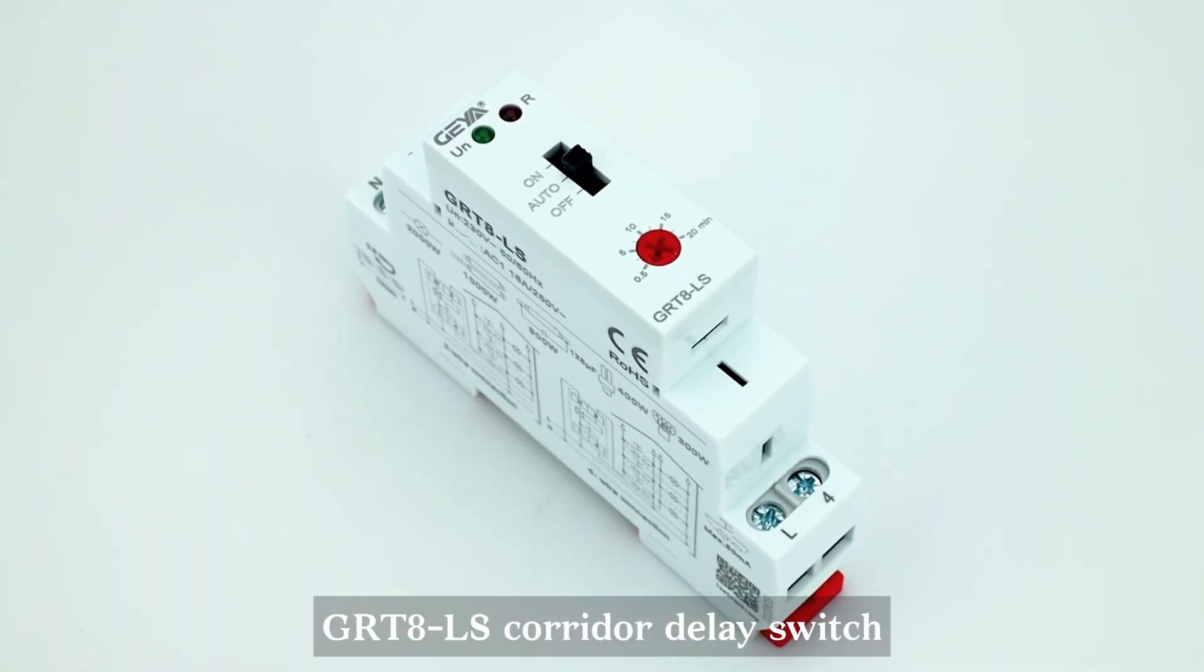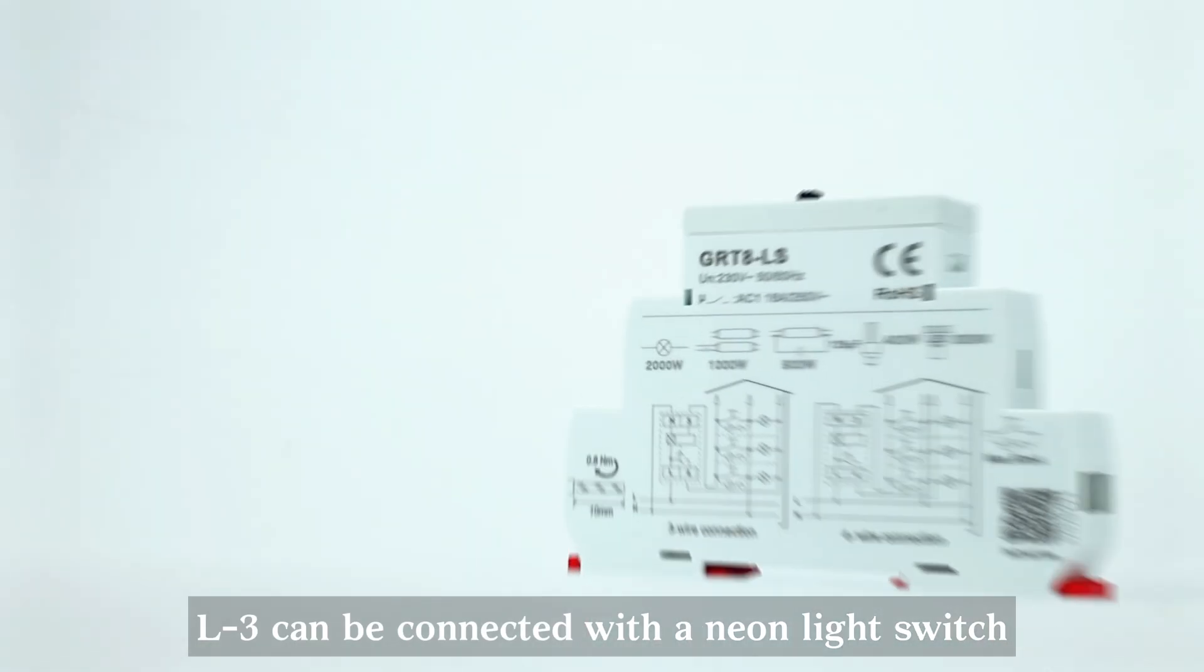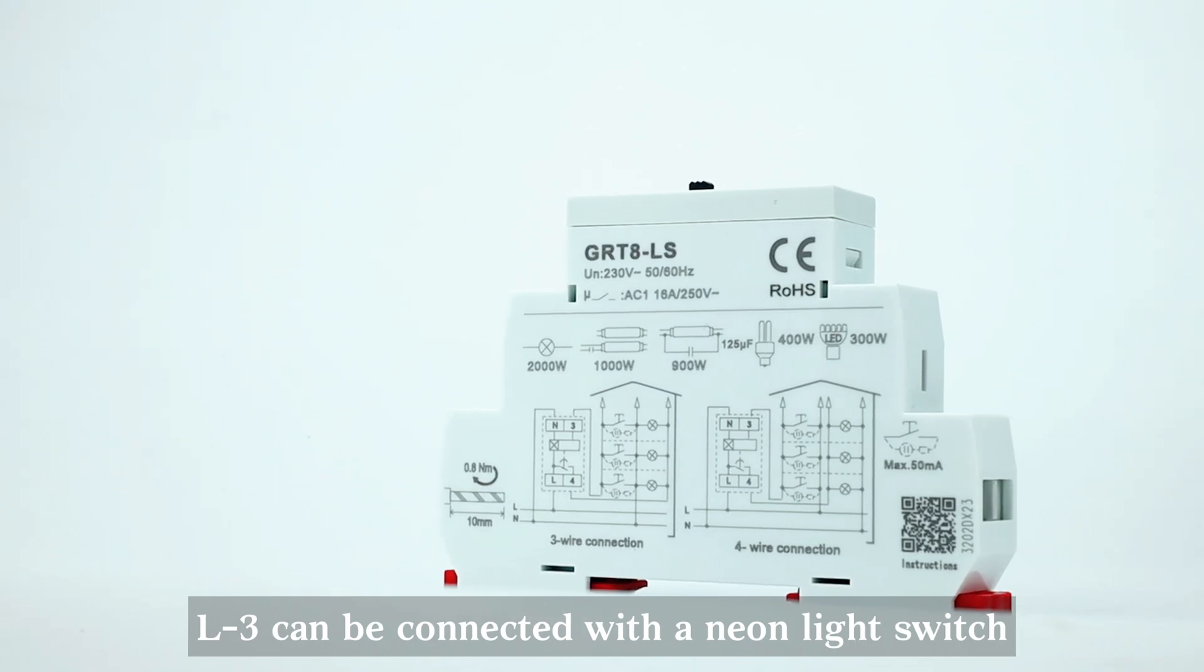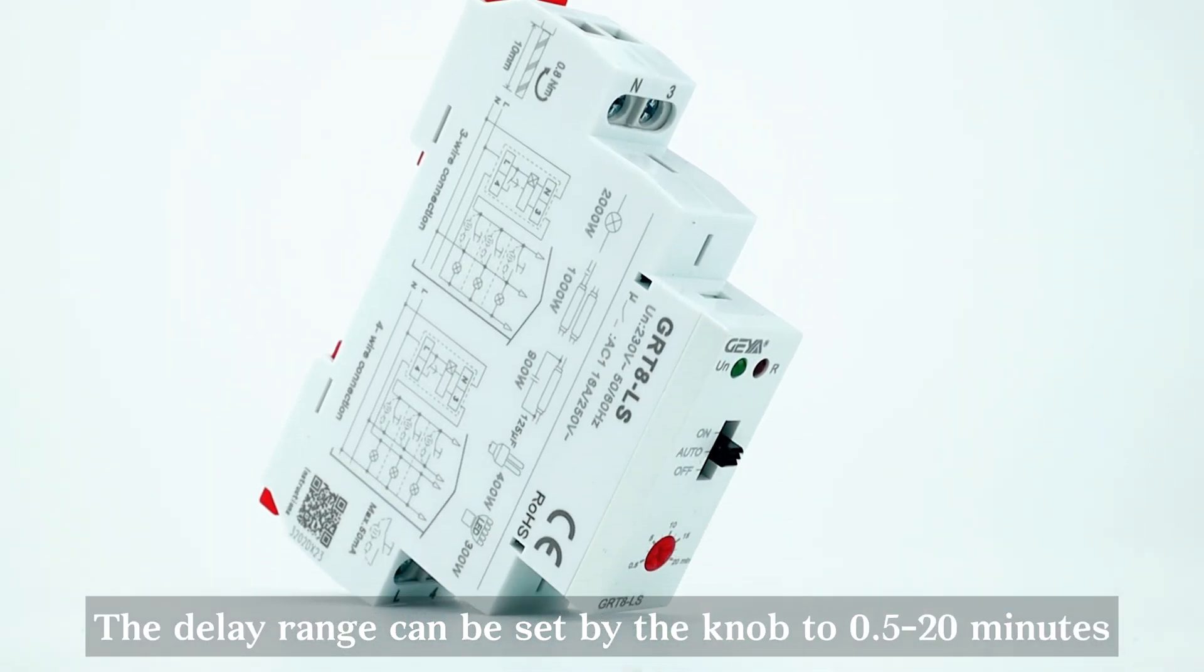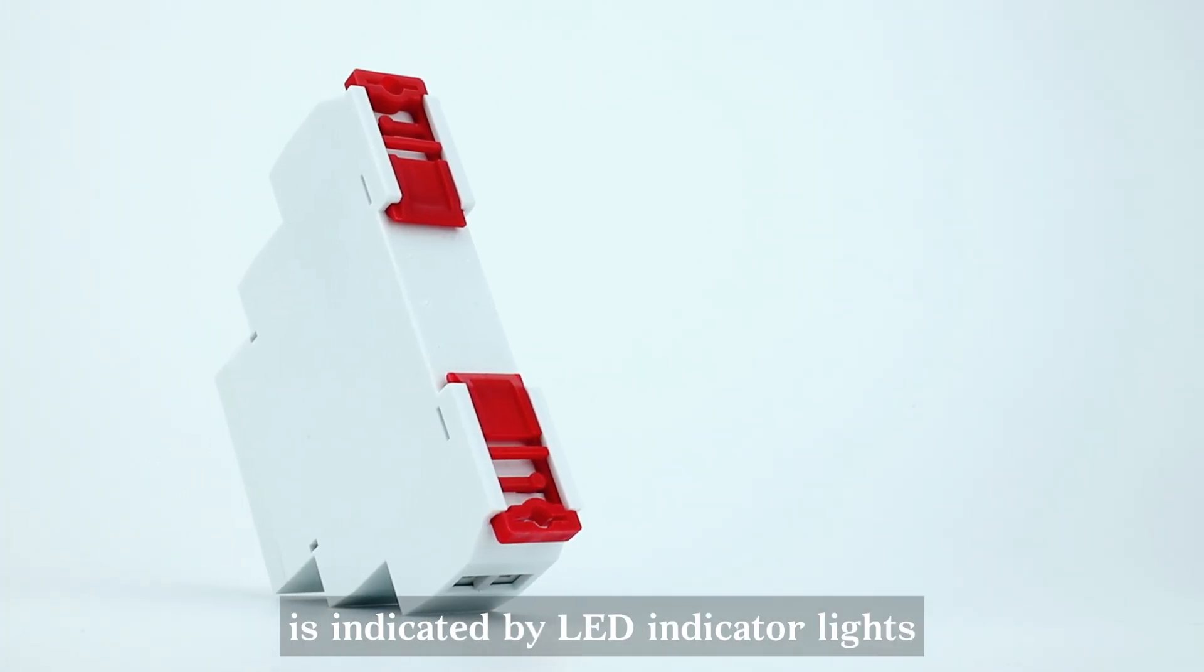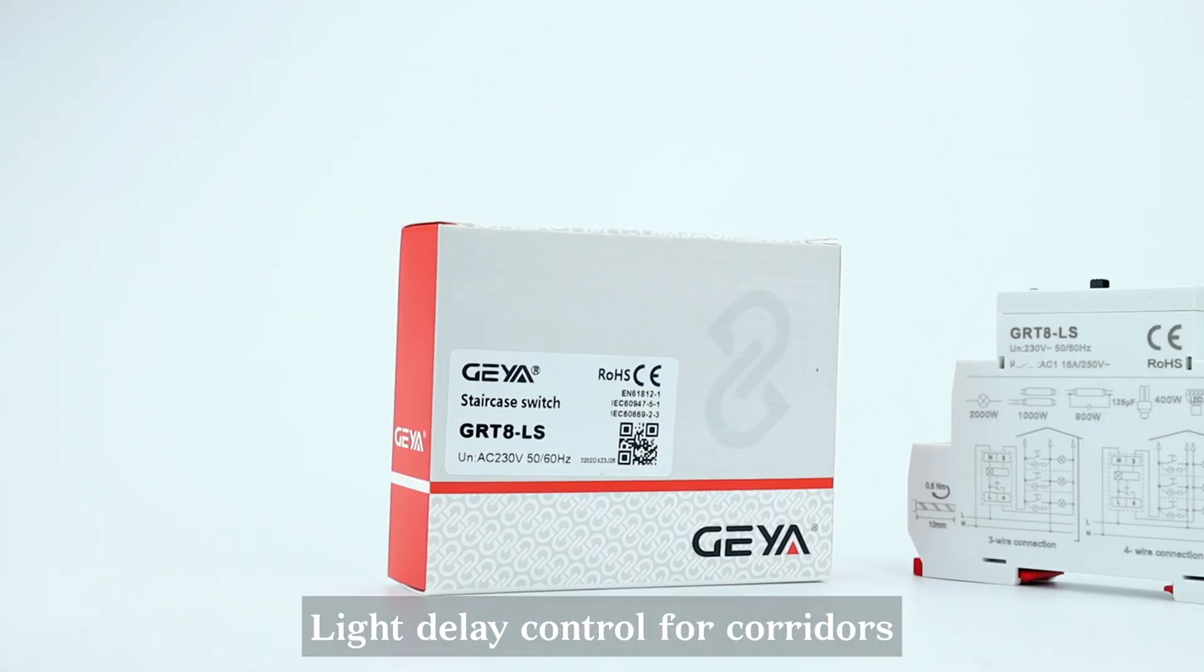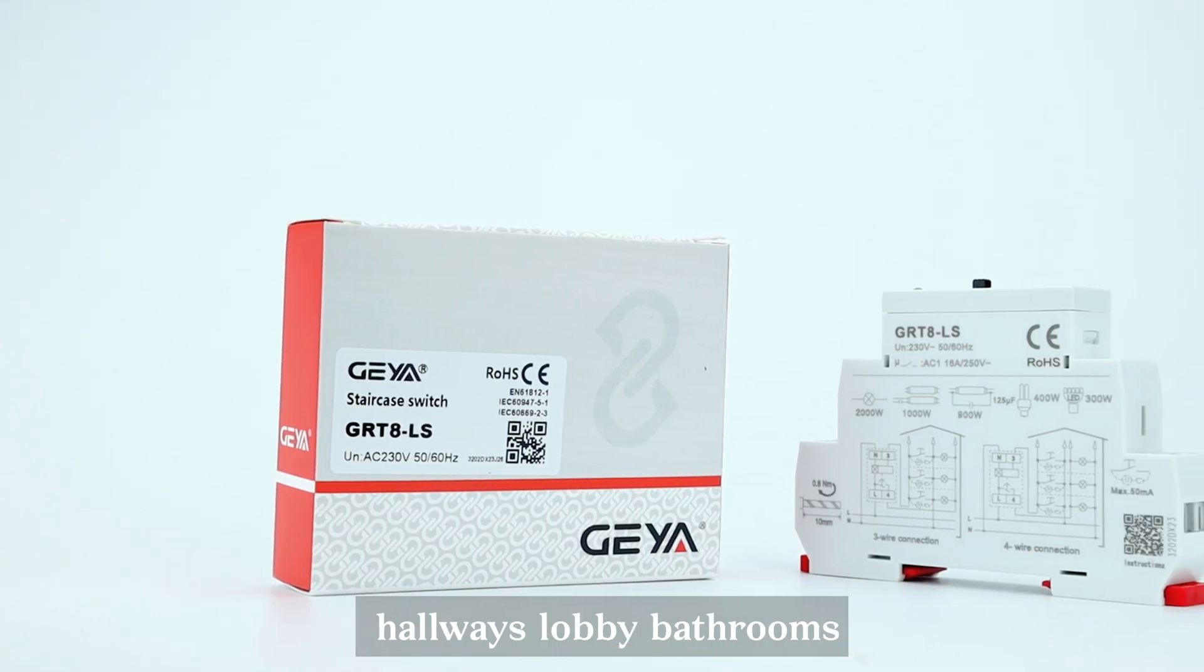The GRT8 LS Corridor Delay Switch has three working modes. L3 can be connected with a neon light switch. The delay range can be set by the knob to 0.5 to 20 minutes. The working status of the relay is indicated by LED indicator lights. Light delay control for corridors, hallways, lobbies, and bathrooms.